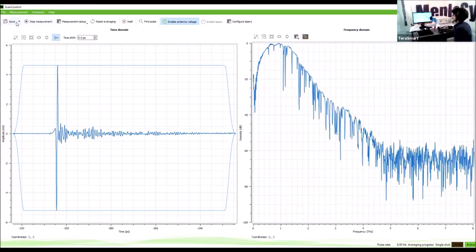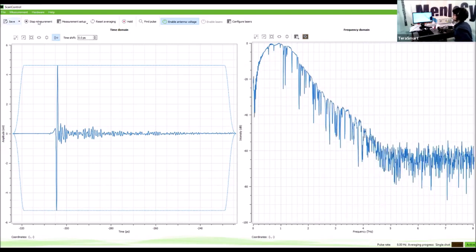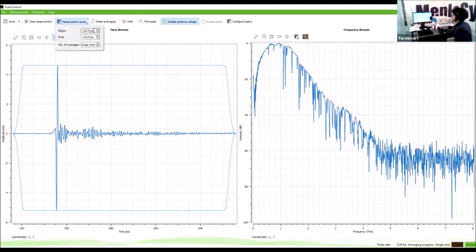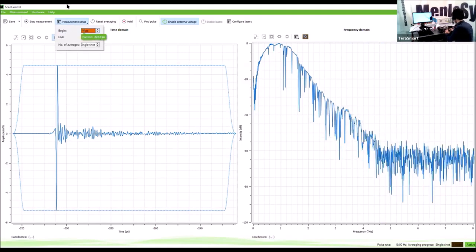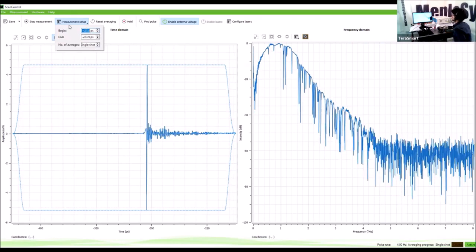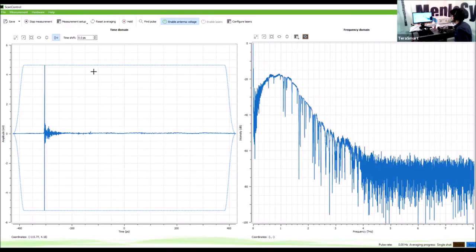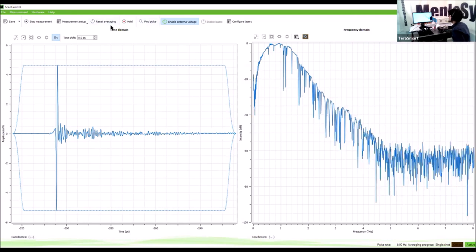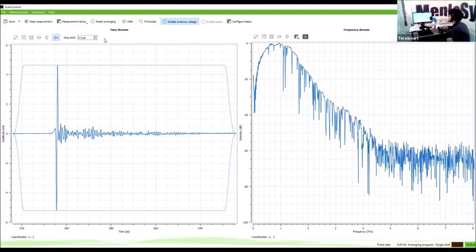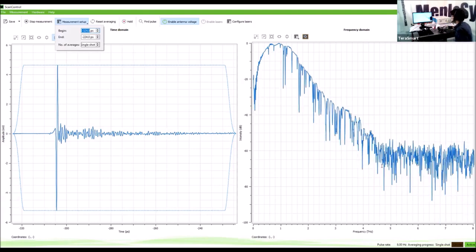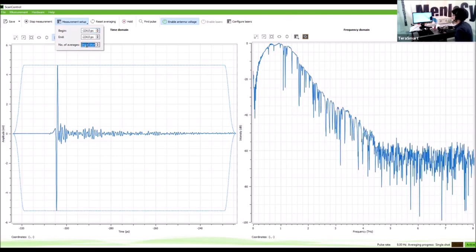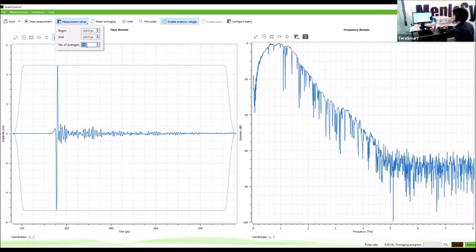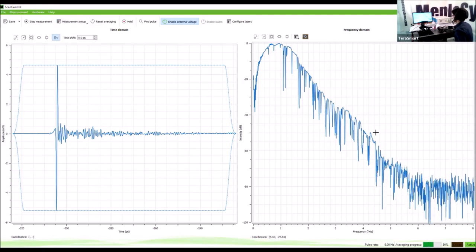For example, what we are seeing here are just water lines. The optics we are using right now, it's a parabolic mirror optic which allows us in single shot to have already a bandwidth of over 4 terahertz. As you can see, comparing the data we see here with some spectroscopy database of the water lines. The interface of the software allows you the basic functions. You can save the data, you can start and stop scan. You can set up the scan parameters live, meaning that the instrument will adjust the parameters of the scan while scanning in a dynamic way.